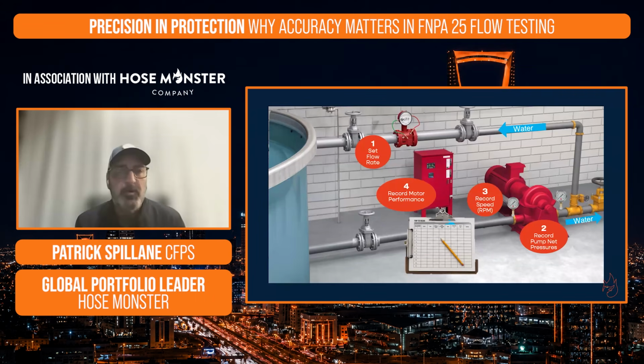So as we look at our fire pump room here, there's a few things that we're going to be documenting when we do our flow test. We're going to want to record our fire pump net pressures. Again, that's going to be your static or your suction pressure versus your discharge pressure. Discharge minus suction creates your net pressure. We're going to want to record our speed, and we're going to record our motor performance. Our motor performance is going to vary depending on whether it's an electric motor or a diesel engine that's feeding that fire pump. And we need to be able to document those results at each flow point.